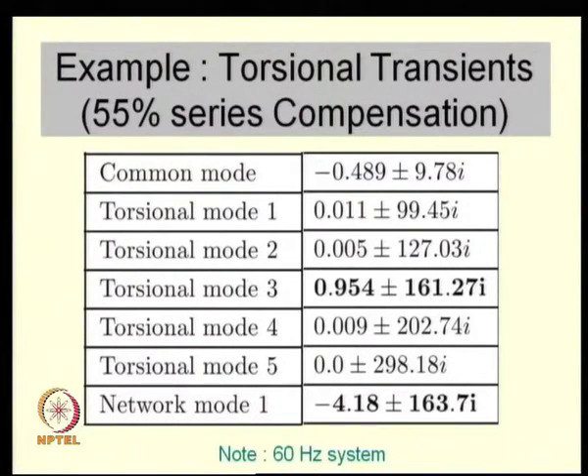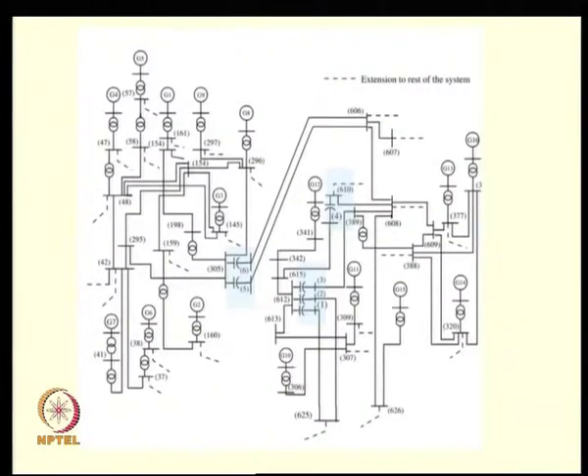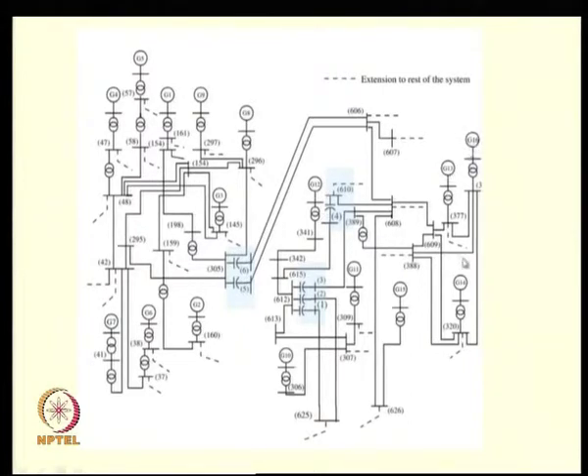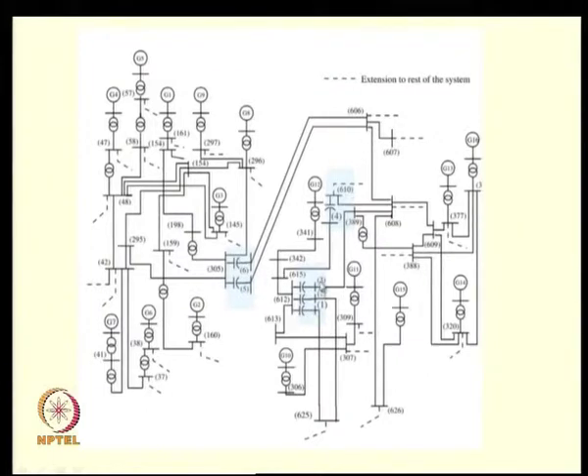There are other practical situations to consider. For example, you can have several series-compensated lines — say 1 through 6 — in a network with several generators, where each generator may actually represent several units of a power plant. You can then have many sub-synchronous network modes and many torsional modes. A linearized analysis is needed to check the actual effect of all these network modes on individual turbine-generator shafts.